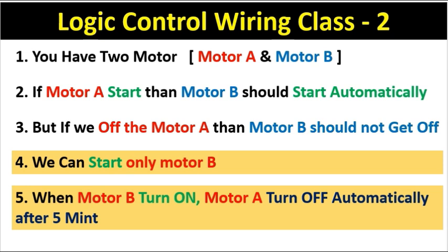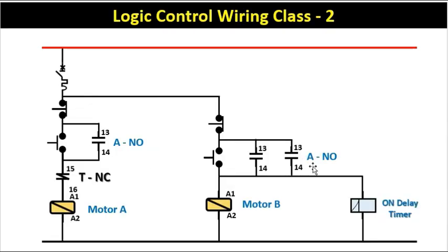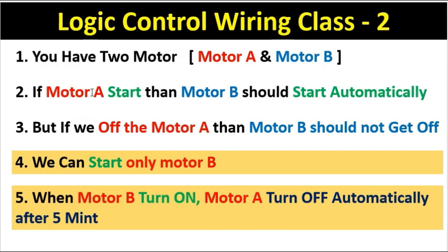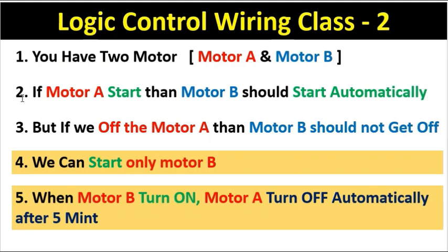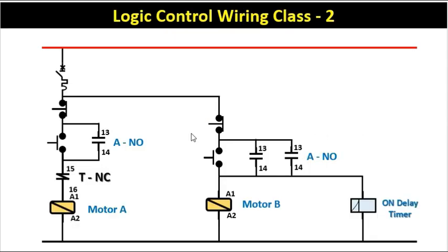So all five logics have been used in this circuit. We have two motors, each with a different starter. If motor A starts, motor B starts automatically — for this, we used the NO contact of motor A's contactor. When motor A turns on, this contact becomes NC, power supply flows, and motor B turns on. Logic 2 is completed. In logic 3, if motor A turns off, motor B should not turn off — and since power supply still flows from the holding circuit, motor B remains on.